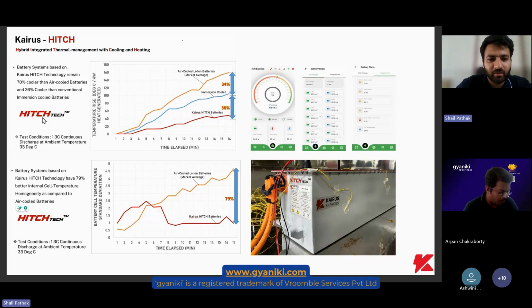Air-cooled batteries, after the test, reached very high temperatures. Kairus batteries were almost 70% cooler after a single cycle. Similarly, in the standard deviation, Kairus batteries were 79% less deviating in temperature, so we were at a band of 1 degree over the entire cell stack.